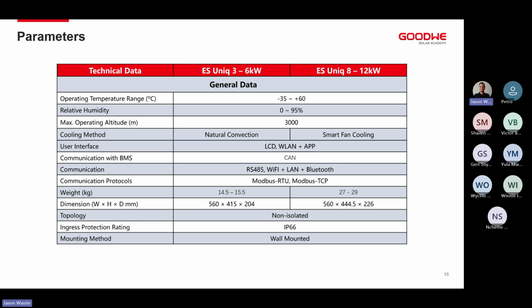When it comes to the larger units, where we've got a lot higher DC-AC conversion and a lot higher amounts of power running through the systems, we do need that additional cooling. So on the 8, 10, and 12 kilowatt units, we've got smart fan cooling. However, these smart fans will only turn on when the inverter reaches 60 degrees Celsius, and will turn themselves off when the internal temperature reaches around 50 to 52 degrees Celsius.